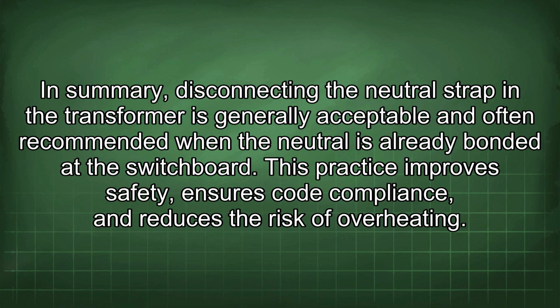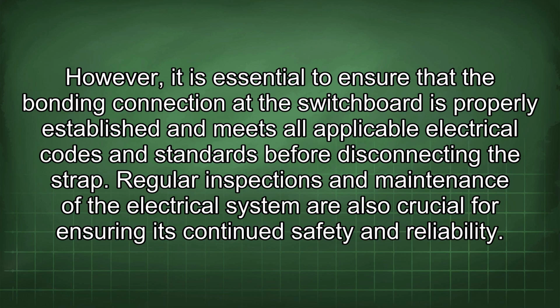In summary, disconnecting the neutral strap in the transformer is generally acceptable and often recommended when the neutral is already bonded at the switchboard. This practice improves safety, ensures code compliance, and reduces the risk of overheating. However, it is essential to ensure that the bonding connection at the switchboard is properly established and meets all applicable electrical codes and standards before disconnecting the strap. Regular inspections and maintenance of the electrical system are also crucial for ensuring its continued safety and reliability.